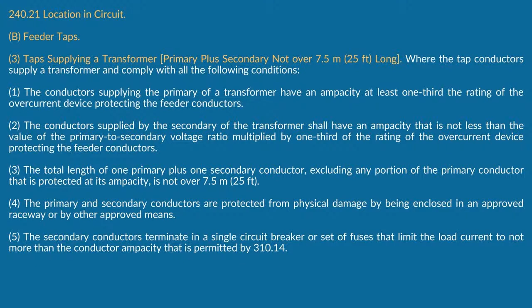I've got a 300 amp overcurrent device upstream. Take it at a third, gives you 100 amps. I go over and look at table 310.16. I need a number 1.